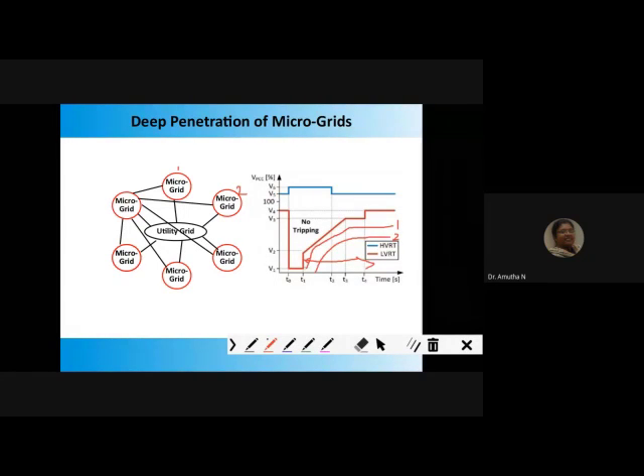Because the microgrid is going to supply some power during the off period also, right? So microgrids may have different characteristics within them. So it is expected that the relay, when compared to the conventional relay, if microgrids are going to penetrate, will not have a single characteristic or one or two characteristics. It is going to be a series of characteristics. It has to adapt to the market demands as well as the grid demands, and it has to be economical also. These three factors are going to decide the relay characteristics of your microgrid.